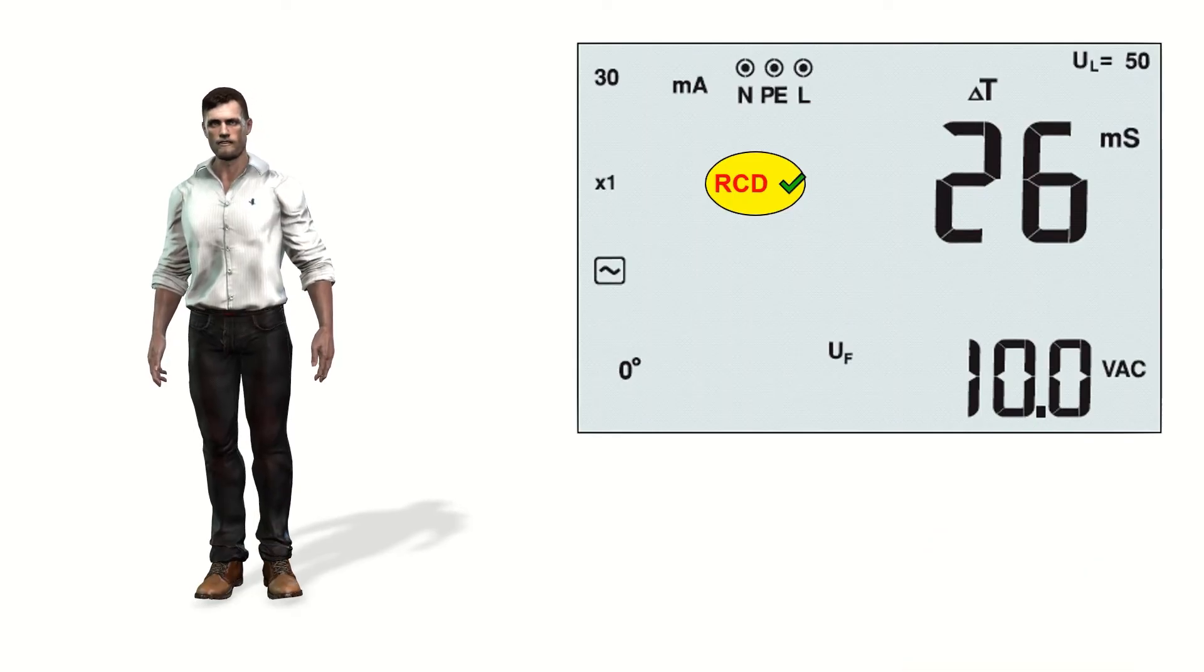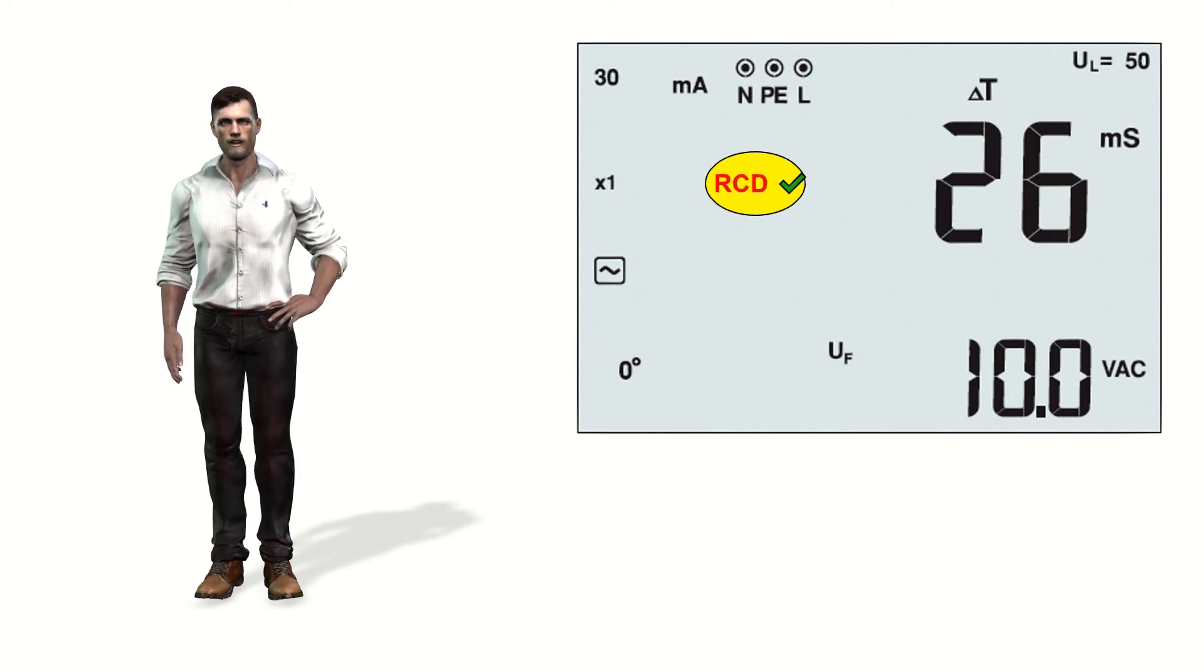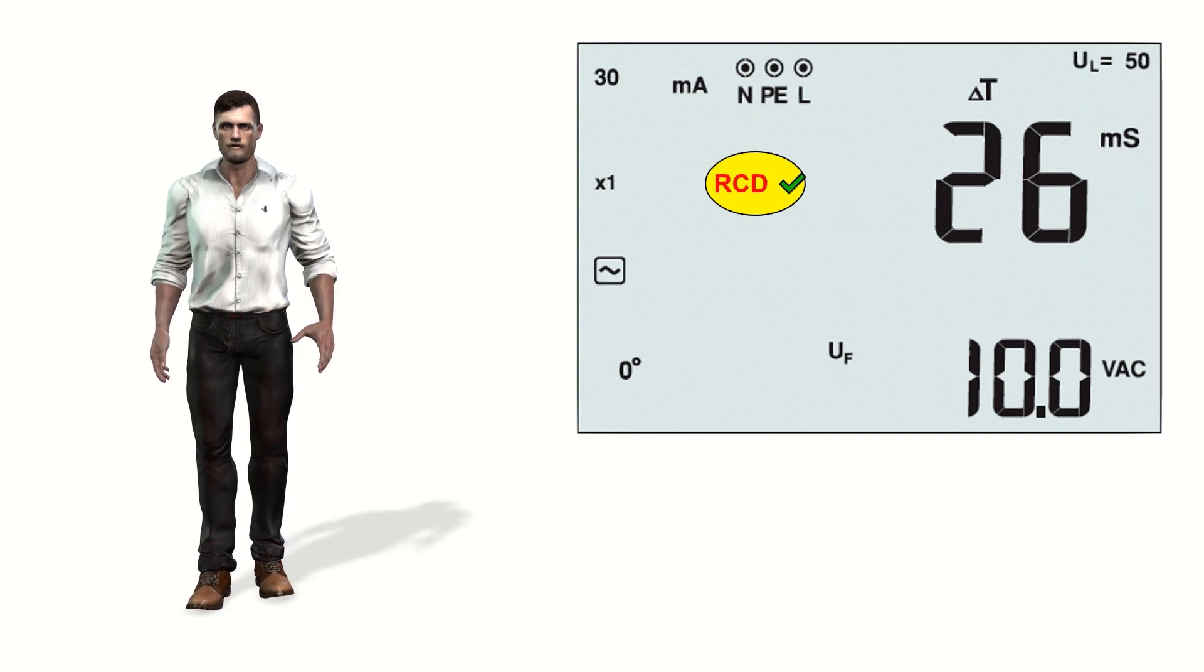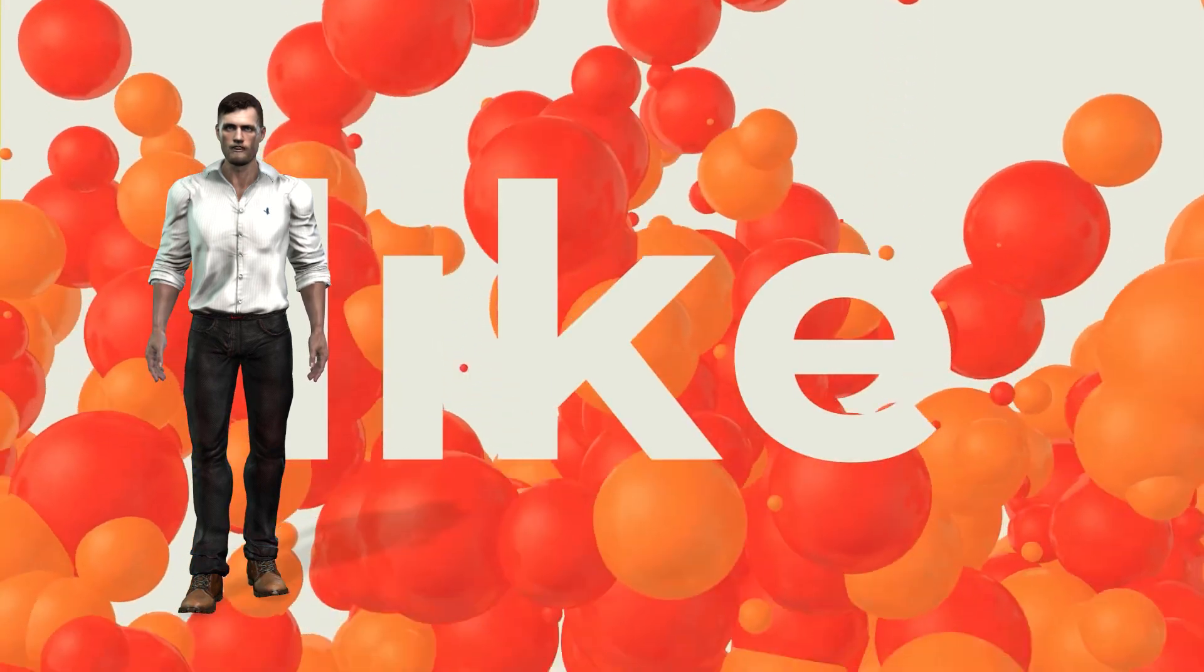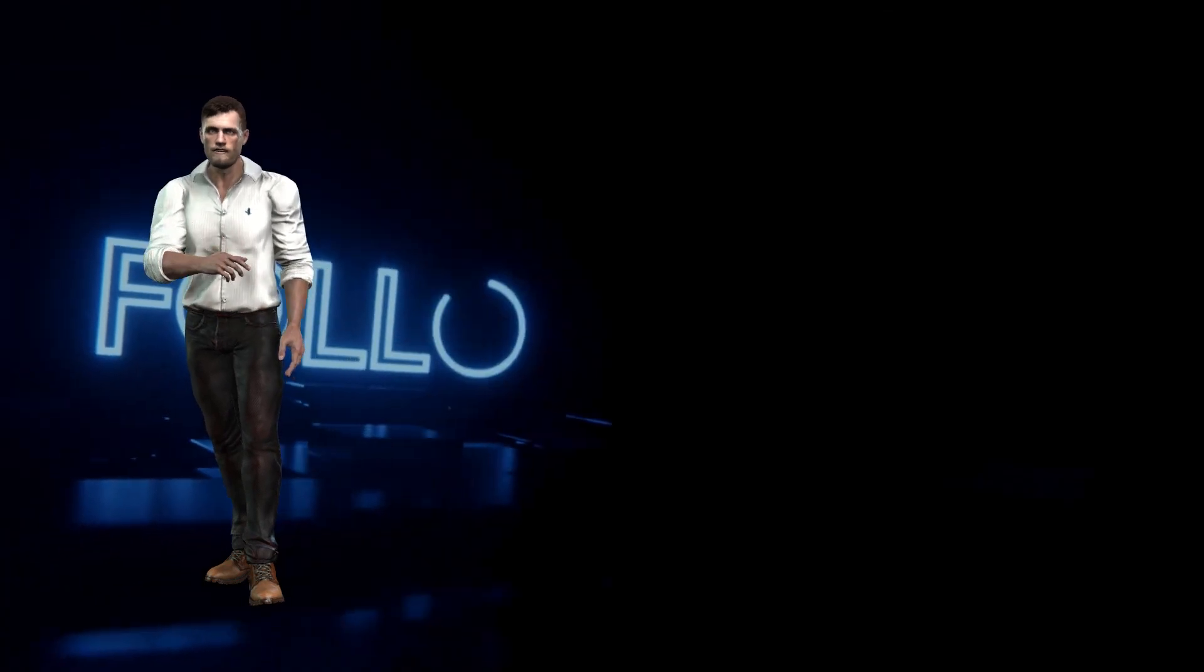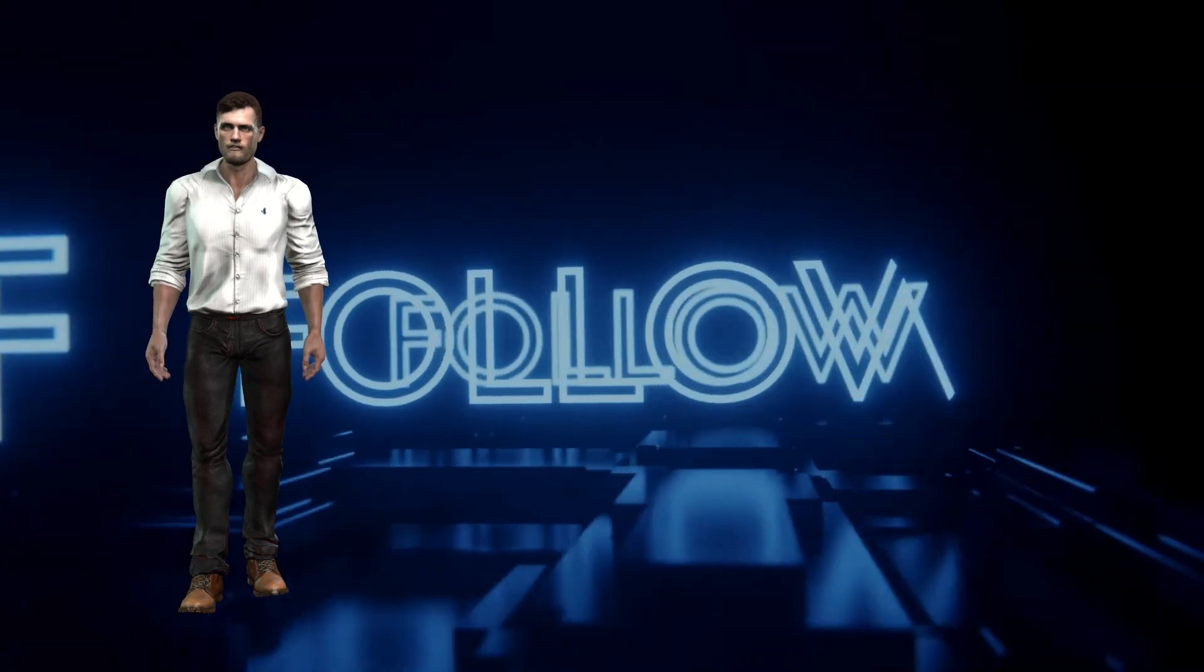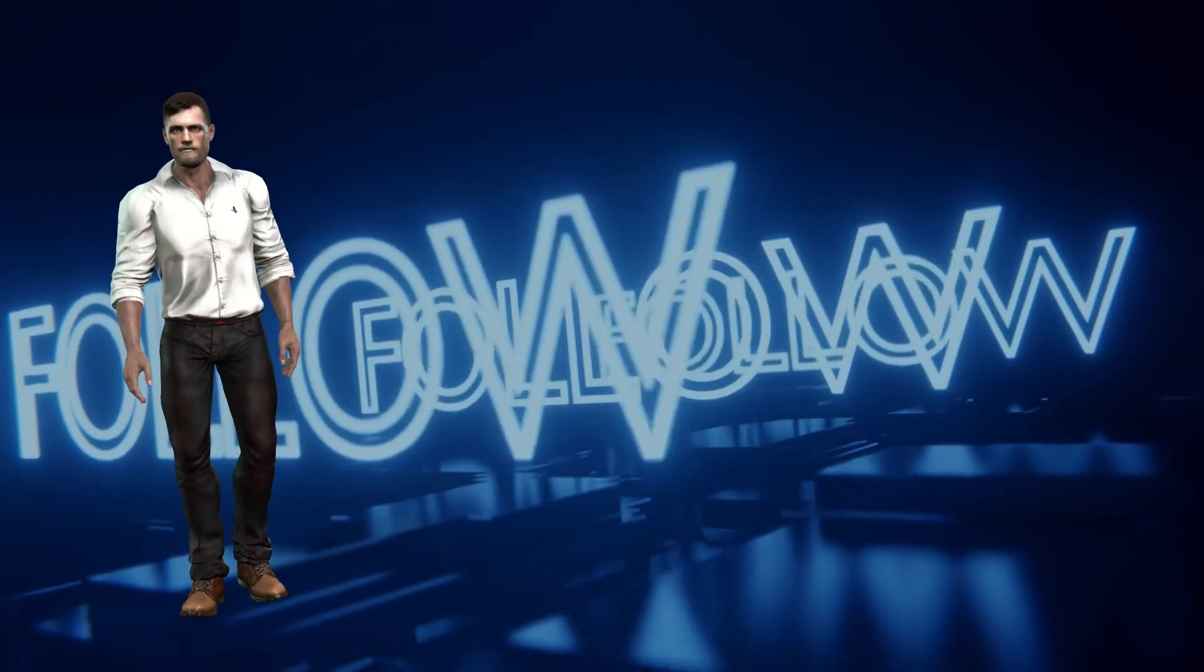In the case of a multifunction tester of the Fluke 1660 series, the instrument itself will show us on the display with a pass symbol, if the differential complies with the maximum opening times mentioned above. And so, we have reached the end of this presentation that I hope you have found interesting. If that is the case, don't forget to drop a like, so that I know that you liked it. In a future video I will show you more aspects related to differential protections, so if you don't want to miss it, don't forget to subscribe to this channel and activate the notification bell. See you in a next video. Bye.